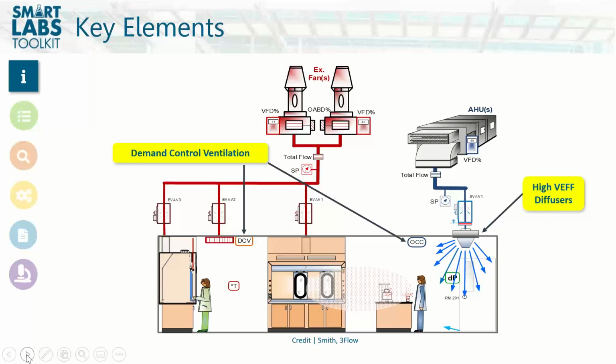So as part of this ventilation control system, we can do what's called demand control ventilation, or setting the ventilation rate based on the occupancy in the space. It'd be very common to have a different occupied versus unoccupied flow, and possibly through looking at the air quality in the space, like total VOCs type thing. So next slide, please.